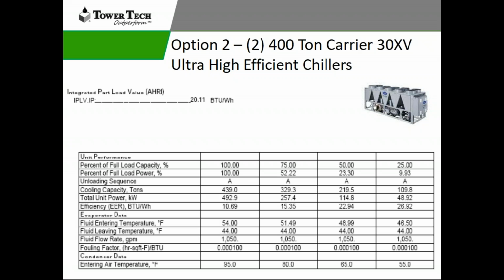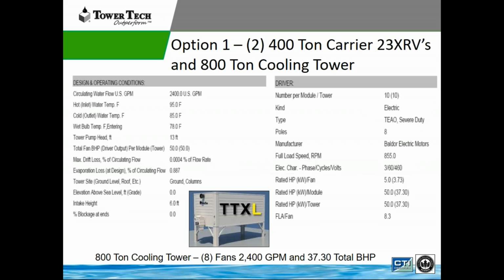And actually, one of the things I didn't discuss is the way this thing ships, and this is what's unique about the installation. I didn't even hit this in the presentation, and I'll show it in a picture here. If you look at this picture of the cooling tower, those legs, we have entered into a new design where when it ships, those legs now fold up on the tower. So when the unit comes off a truck, it actually pulls up, you fold down the legs and you put it in place. If anybody has installed a traditional tower system where you have the basin and then you have the tower you have to stack on top, you have to make sure it's completely aligned and all the gaskets and everything is in place. So from an install standpoint, it's easier, but as a whole, weights are very similar to a traditional system.